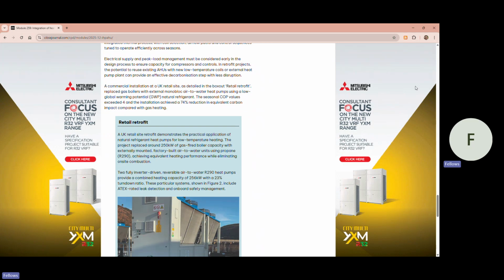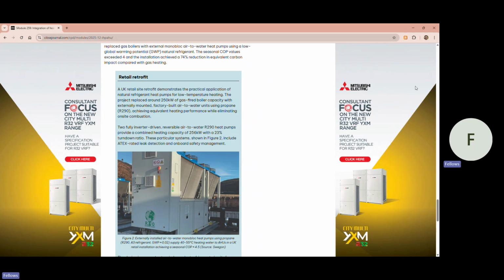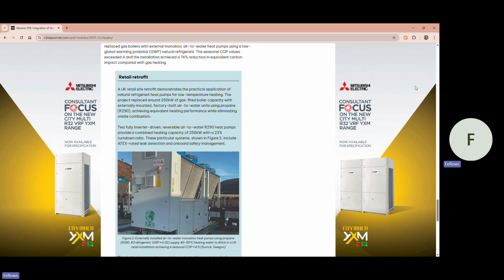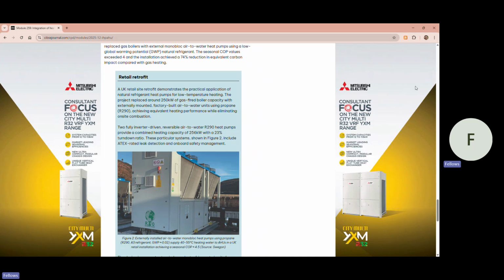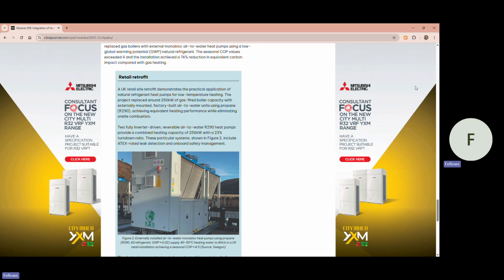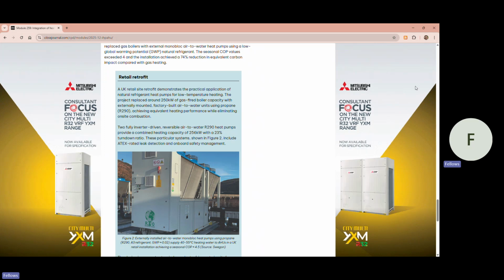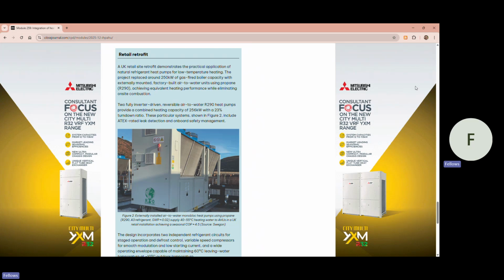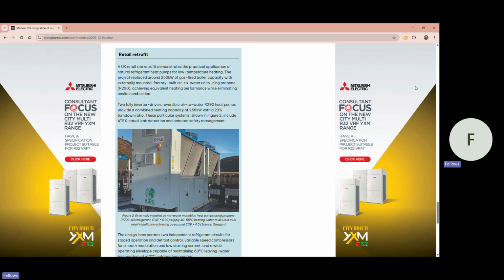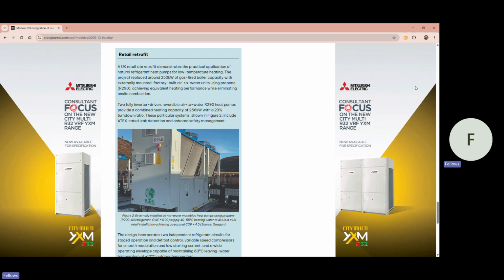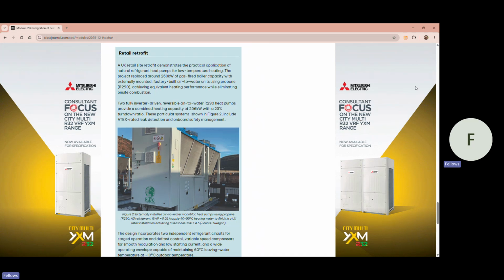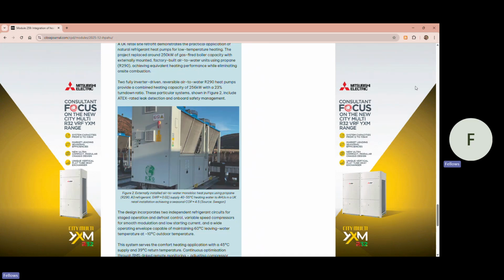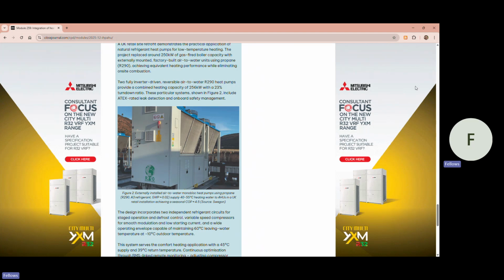Retail retrofit. A UK retail site retrofit demonstrates the practical application of natural refrigerant heat pumps for low temperature heating. The project replaced around 250 kilowatts of gas-fired boiler capacity with externally mounted, factory-built air-to-water units using propane, or R290, achieving equivalent heating performance while eliminating on-site combustion. Two fully inverter-driven reversible air-to-water R290 heat pumps provide a combined heat capacity of 256 kilowatts, with a 23% turndown ratio. These particular systems, shown in Figure 2, include ATEX-rated leak detection and onboard safety management.